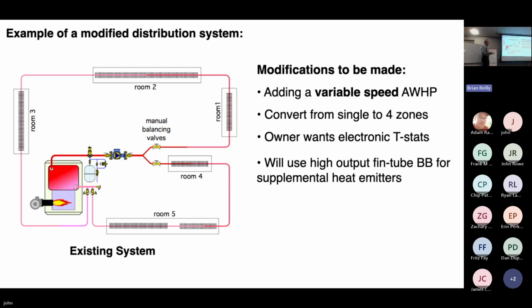So let's say we're going to add a variable speed air-to-water heat pump. We're going to convert from single to 4 zones. This is all a single zone system. Some thermostat somewhere in the house, one thermostat, turns that circulator on and enables the boiler to fire. But let's say the owner wants to go to 4 zones. And the owner wants to use electric or electronic thermostats.